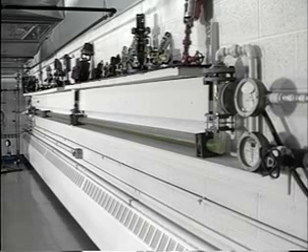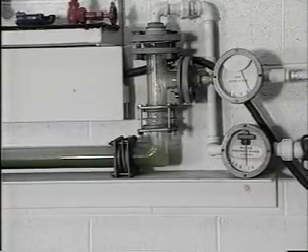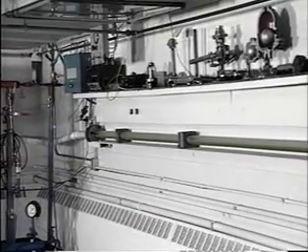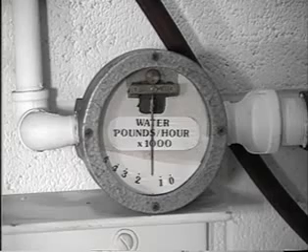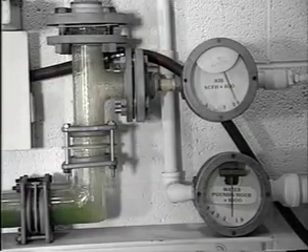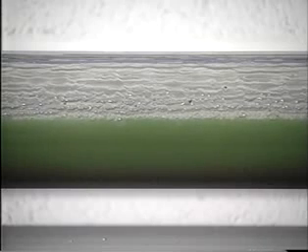In the demo lab at Armstrong International, we have assembled a fixture to illustrate the problem. We use this twenty-foot, two-inch diameter glass pipe to act as a condensate return line. The pipe is pitched one-quarter inch in ten feet to provide gravity flow. Flowing through the pipe, we have cold water. In addition to water, we can also have compressed air flowing in the system to simulate flash steam flowing across the top of the condensate by virtue of differential pressure. One flow meter constantly measures the flow rate of the water. Another flow meter continuously monitors the flow rate of the compressed air. As you can see, we now have fifteen hundred pounds per hour of water flowing in our glass pipe and no compressed air. Under this condition, our pipe is approximately half filled with water.